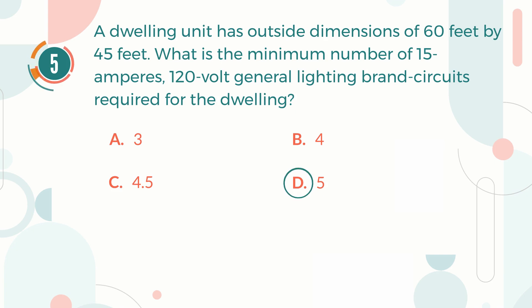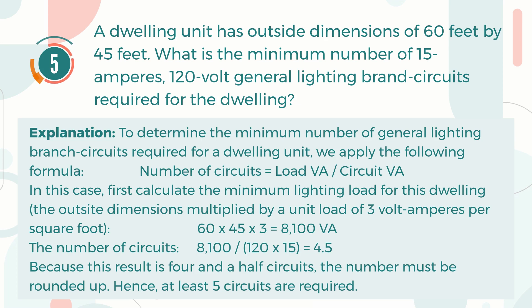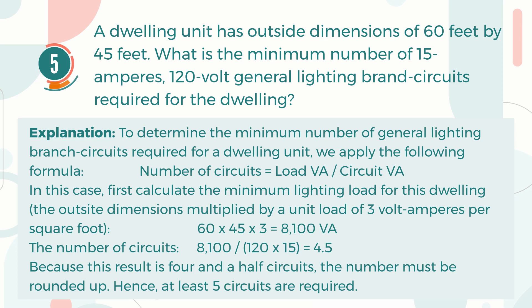The correct answer is D. 5. Explanation: To determine the minimum number of general lighting branch circuits required for a dwelling unit, we apply the formula: number of circuits equals the load in volt-amperes divided by the circuit in volt-amperes. First, calculate the minimum lighting load: outside dimensions multiplied by a unit load of 3 volt-amperes per square foot equals 8,100 volt-amperes. Number of circuits equals 8,100 divided by (120 × 15) equals 4.5. Because this result is 4 and a half circuits, the number must be rounded up. Hence, at least 5 circuits are required.